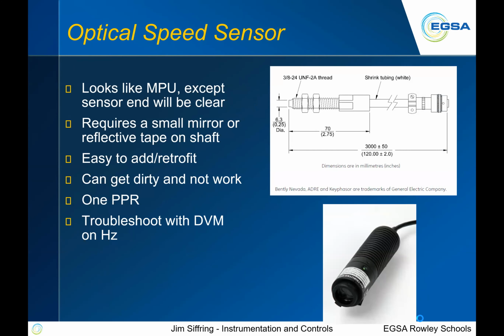Okay, optical speed sensors, similar. Often they look similar to an MPU, but what they do is provide a light source, and they have a device that can receive the light. So a transmitter and a sensor looking at light. It's looking at the reflective light coming back into the device. So if you put this on, say, a shaft or a fan, you'll have to have some sort of reflective material, typically like a piece of white tape on a fan blade, and you can see how many times that fan blade goes by, because it catches the reflection as it turns.